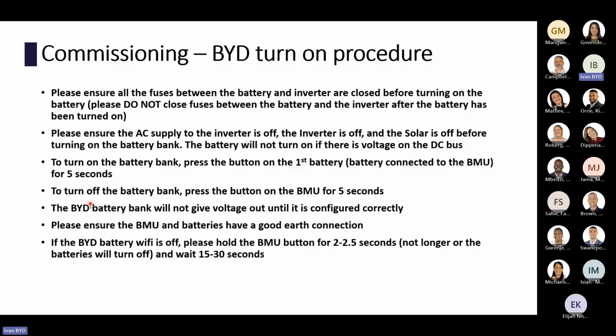Please ensure the BMU and the batteries have a good earth connection. My apologies for repeating it so often, but it's a good thing to keep an eye out for, and that's also true for almost all batteries. If you've got comms issues, it's almost always the earth connection.